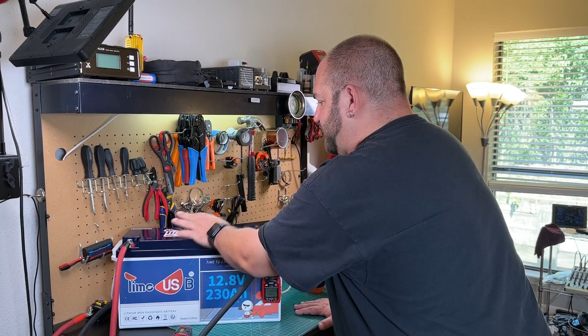After a few minutes at about 270 amps, the BMS did not shut off. Things are warming up a little, but that's more due to the cable not really being rated for that much current. The battery itself doesn't feel very hot at all, but the wires are heating up. Battery's at 88 degrees, terminals at about 100 to 103-ish, but that's because of the cables. Oddly enough, my 250 amp breaker didn't break either, so I might need to look into that.